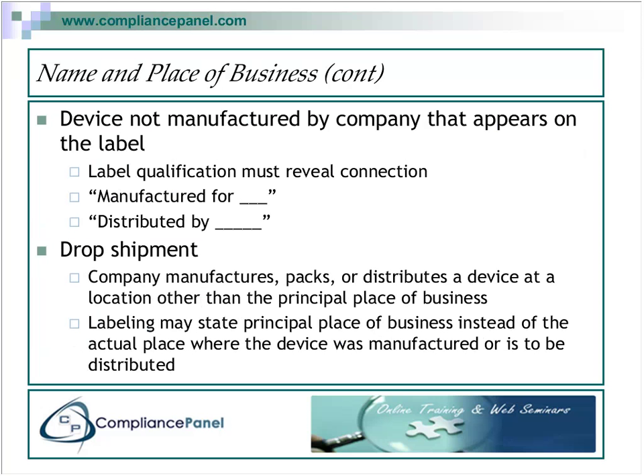Continuing name and place of business. In situations, a device might not be manufactured by a company that appears on the label. In a case like this, the label must reveal the connection. It's got to say something like manufactured for or distributed by. Either of these is acceptable. Both of them is acceptable. You've got to indicate this on your labeling.